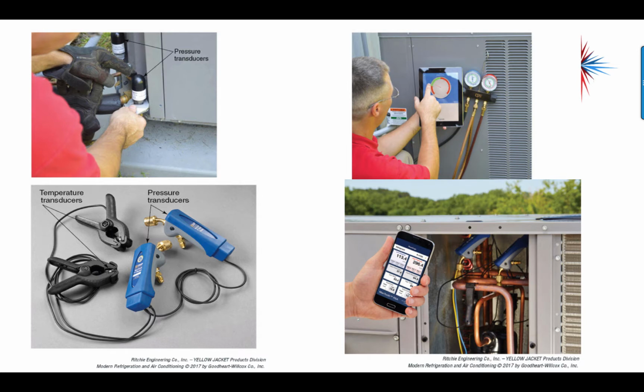So again, this is just someone putting pressure transducers on here. You might have pressure and temperature together, and then you can display these on your digital gauges, okay? Compared with the old style of having to calculate superheat, subcooling, and everything else with the long hoses. Now, one of the benefits of using the transducers with the very short hose alignment we have here is that you do not lose a lot of refrigerant, yet you have a lower chance of putting contaminants into the system you're testing.